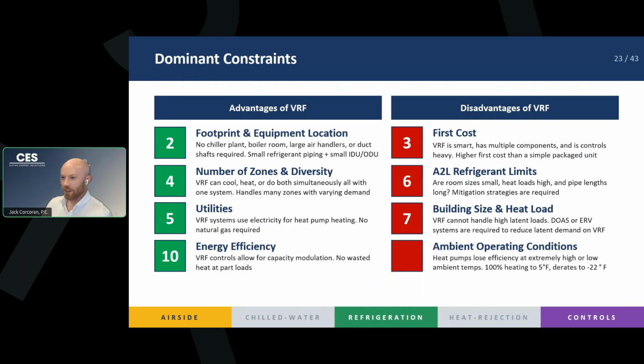Another major advantage of VRF, as we said, it can heat, cool, and do both at the same time, right? So if you have many different types of zones and the diversity between them, as I said, you're going to have sunny zones, you're going to have shady zones, you might have a huge conference room, or you might have a little phone booth or storage closet. Those are going to have very different load profiles. VRF is flexible enough where you can send only the amount of refrigerant you need to that small zone, only the amount of refrigerant you need to the big zone, and that'll accomplish the amount of heating and cooling that you need. So it's a pretty powerful tool there if you have multiple zones and all of them require different amounts of heating or cooling.